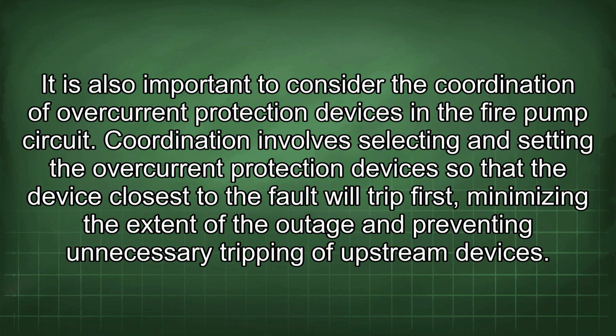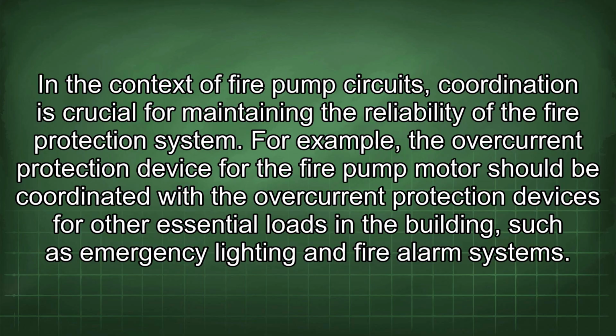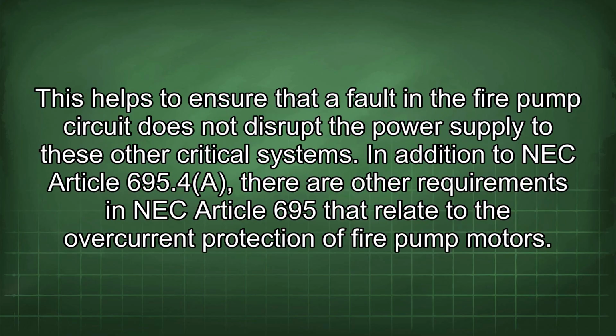It is also important to consider the coordination of overcurrent protection devices in the fire pump circuit. Coordination involves selecting and setting the overcurrent protection devices so that the device closest to the fault will trip first, minimizing the extent of the outage and preventing unnecessary tripping of upstream devices. In the context of fire pump circuits, coordination is crucial for maintaining the reliability of the fire protection system. For example, the overcurrent protection device for the fire pump motor should be coordinated with the overcurrent protection devices for other essential loads in the building, such as emergency lighting and fire alarm systems. This helps to ensure that a fault in the fire pump circuit does not disrupt the power supply to these other critical systems.